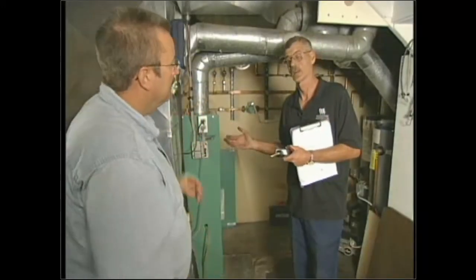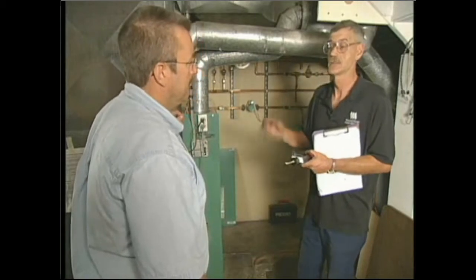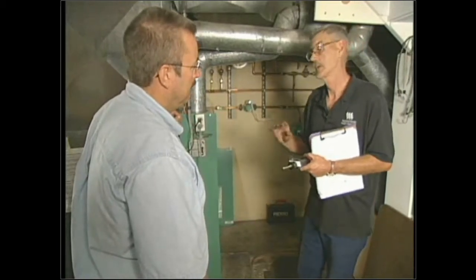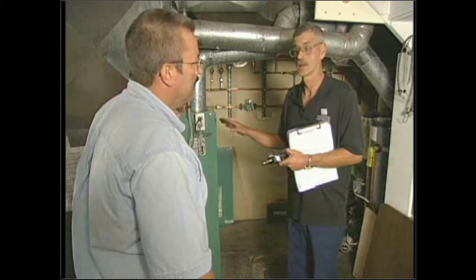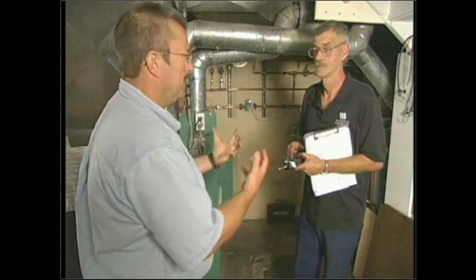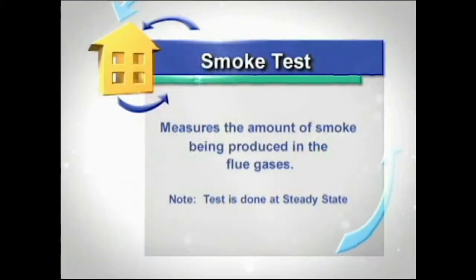Another test an auditor needs to perform is a smoke test. And it's only performed on the oils. It's the only furnace that it is performed on. Okay, so what does a smoke test provide? The smoke test provides us with information on how much smoke is being produced in the flue gases.